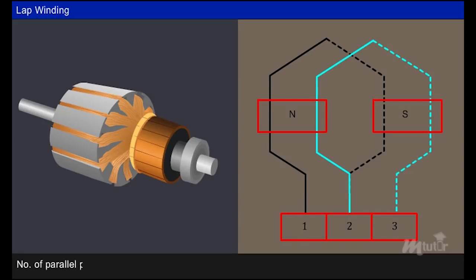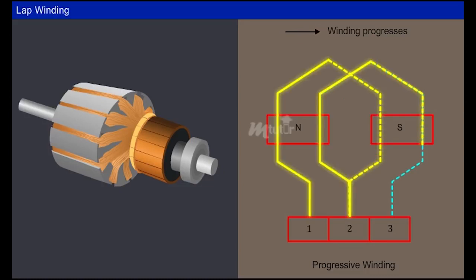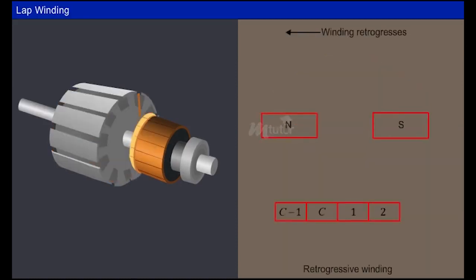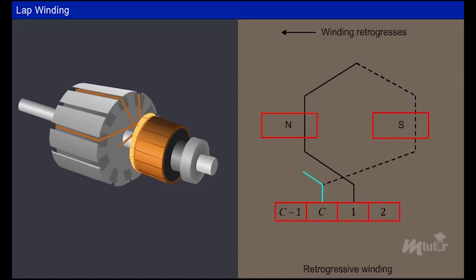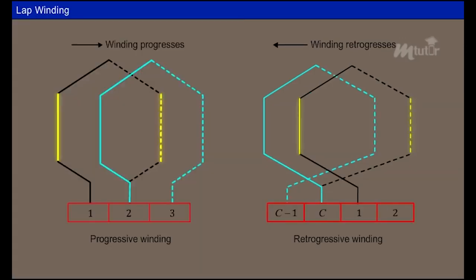The number of parallel paths A of lap winding is equal to the number of poles P. The illustrated armature winding is called progressive winding, as the winding progresses in the direction of the coil wound. The other way of winding is called retrogressive winding, in which the winding progresses in the direction opposite to that of the coil winding direction.